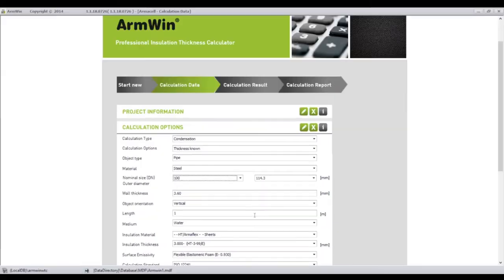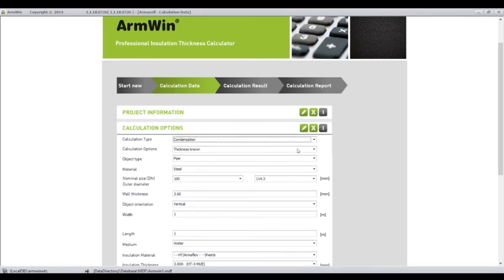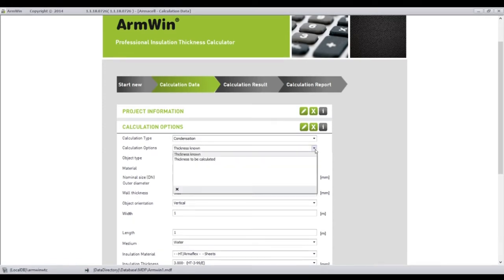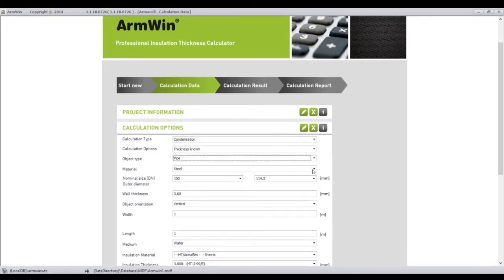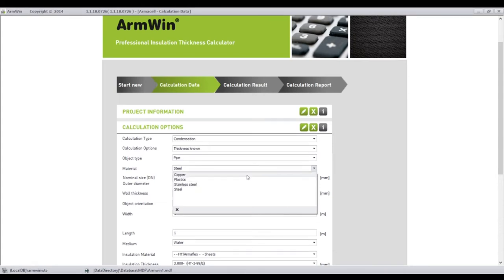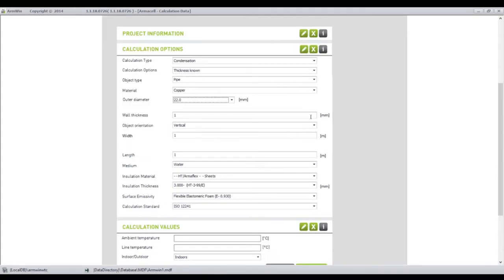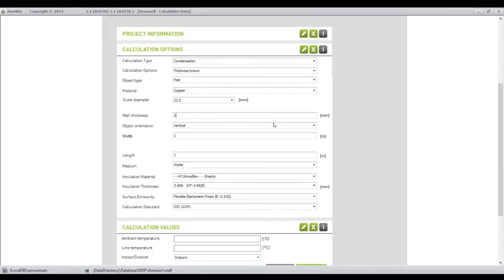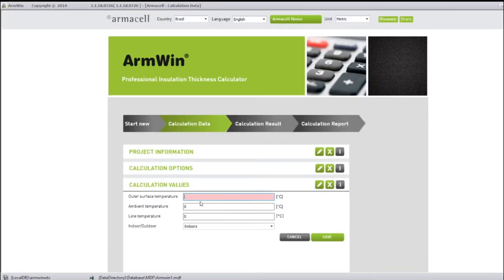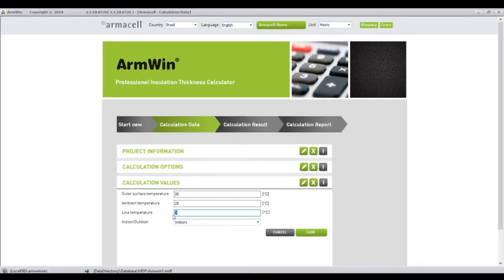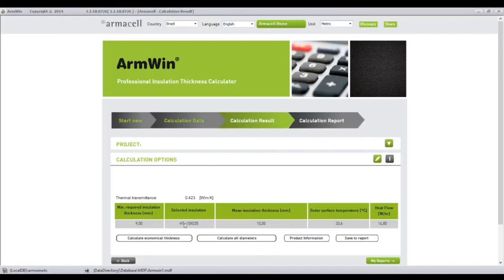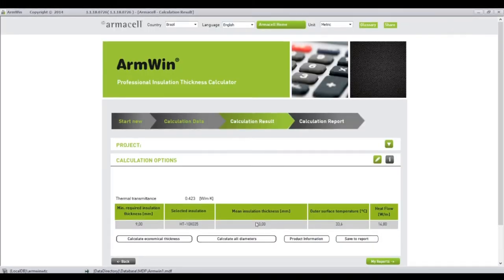However, the ARMWIN software is used to check the economic thickness insulation material for pipes, as shown here. We need just to input the information. I'll just give a roughly information here, just as an idea about how it works. To get the results, I'll put some aleatory information. Here, I can insert surface, ambient temperature, line temperature, there you go. It will give the economic millimeter for the thickness. Knowing this, we can go to the next step.